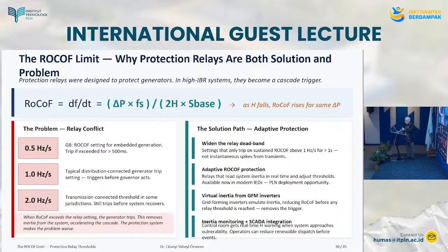Now what is the solution for this in the future? So adaptive protection is one way forward. Widen the relay deadband, so the trip settings, adaptive rate of change of frequency protection, relays that read the system inertia in real time and adjust thresholds. Now these are becoming available, technologically possible, new protection systems.